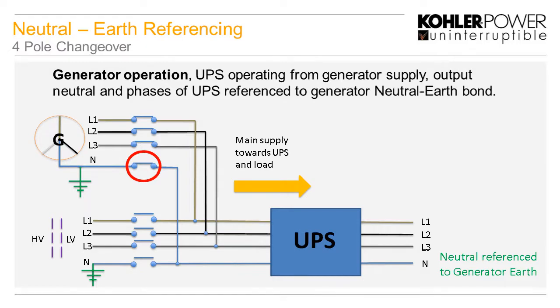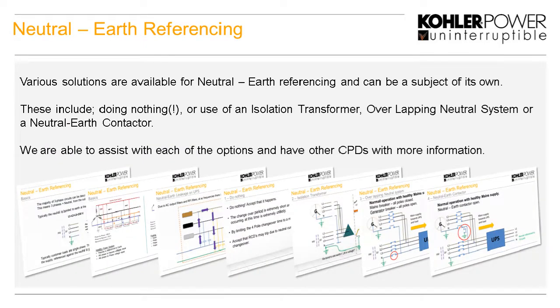Now, this is a big subject. We have different CPDs on that. There's different things we can do. We can limit the changeover. We can use an isolation transformer, galvanic isolation transformer, to recreate a neutral earth point. We can use overlapping neutral systems or neutral earth contactors. Like I say, it's quite a subject. We get a lot of questions about this, but what we're putting over here is an important consideration for you to look at.